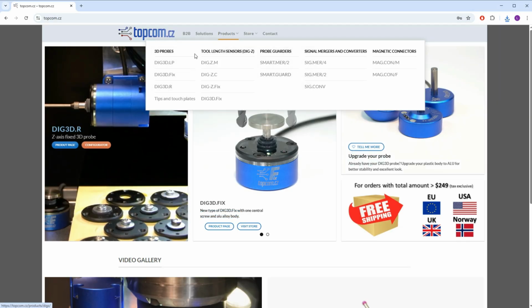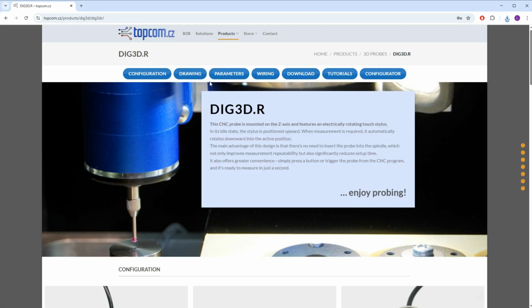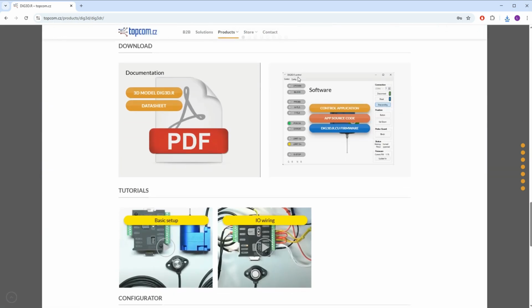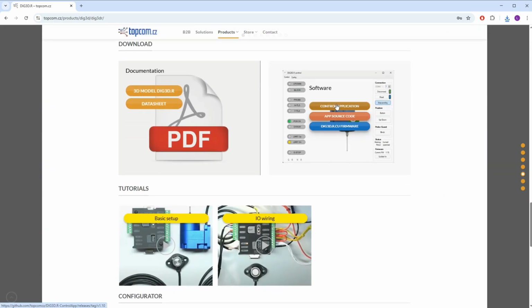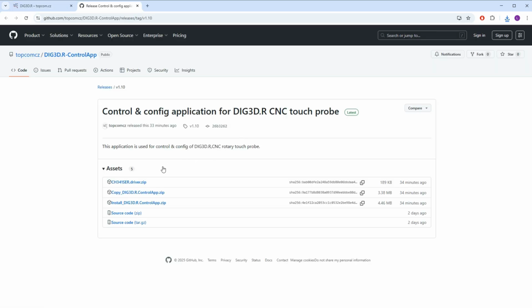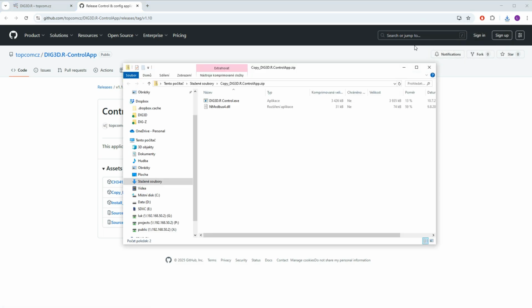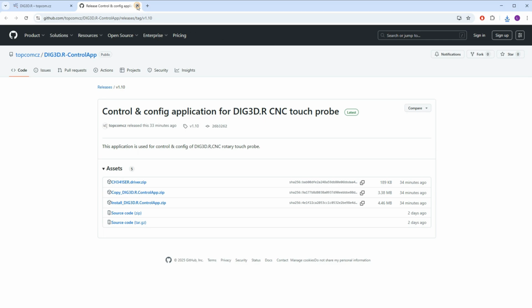Go to the product page at topcom.cz and navigate to the download section. Here you'll find a link to download the application package, which includes the USB to RS-485 converter driver, the application installer, and a set of files for manual use if you prefer not to install the application. The application consists of a single executable file and a library for communication via the Modbus protocol. You simply need to copy the files into your target directory.